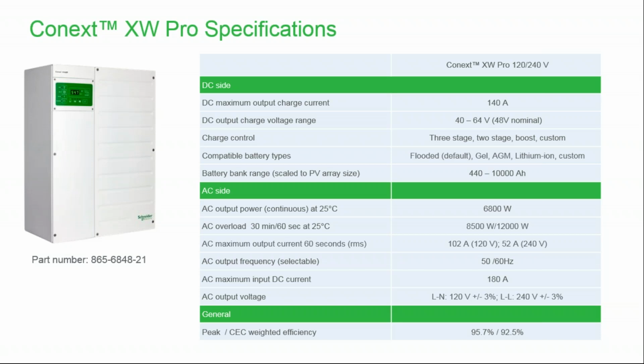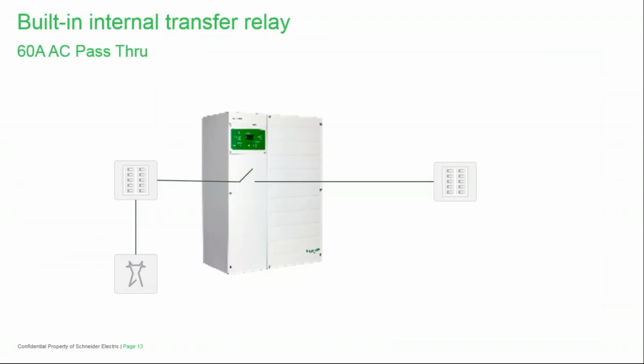The fourth thing that it does is it has an internal transfer switch, which allows you to feed the grid power directly through the inverter to the loads. And then some of that grid power, quite a bit of it actually, can be used to power the battery charger. The 60 amp pass-through is also about 8 milliseconds. So we don't see any loss of power to the loads when we do the switching.